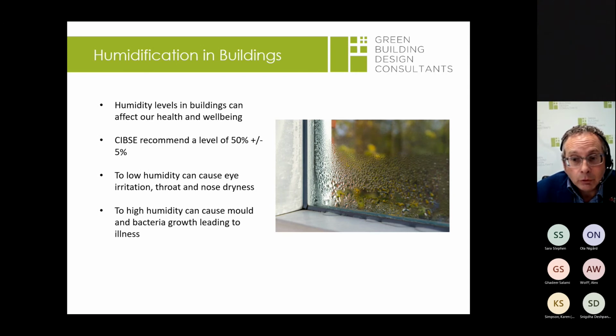Now, as I said, the USA are recommending this 40 to 60% criteria internally for health reasons. Whereas we were on that correct path in the 70s and 80s, most buildings now have really had that humidification switched off, unless it's something very specific like a clean room process, or maybe a laboratory which is wanting it, or some parts of hospitals where they're more asking for that level of humidity.